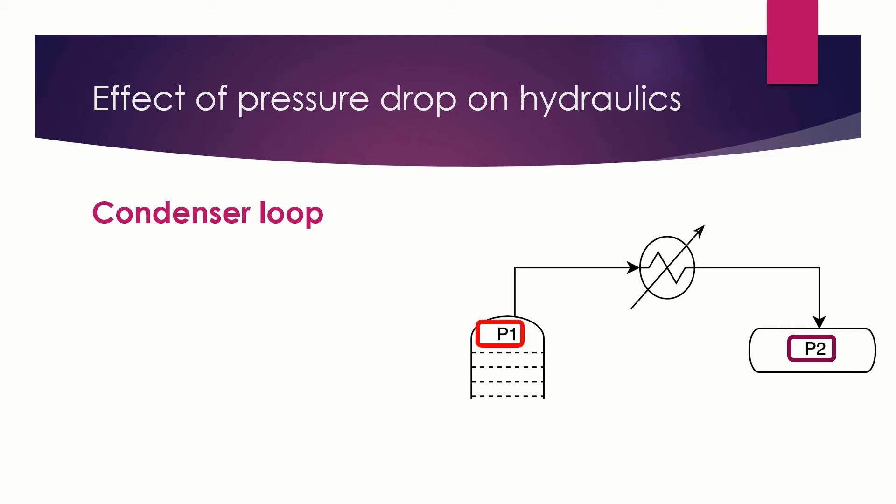In order that the vapor flows from the tower to the vessel at the flow we want, then the difference between P1 and P2 should be greater than the sum of the pressure drop in this pipe, the pressure drop in the condenser, and the pressure drop in the last pipe.